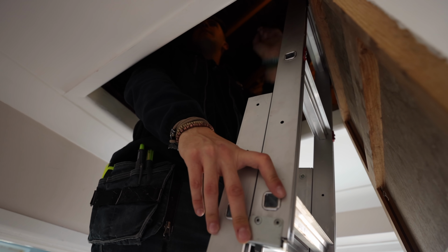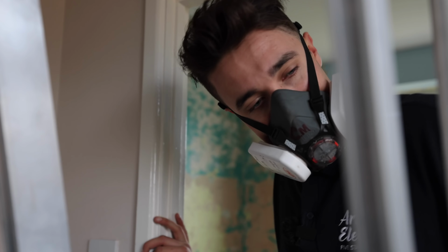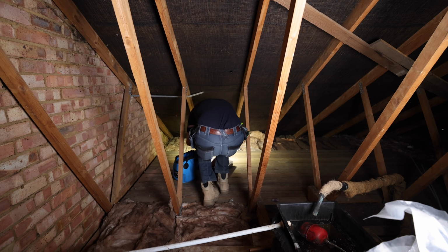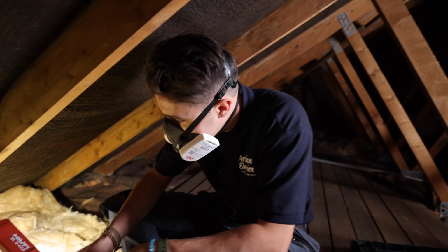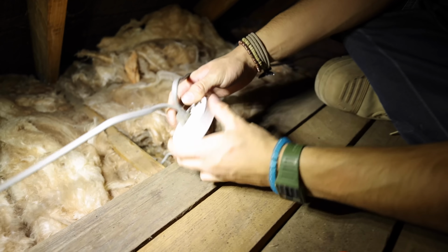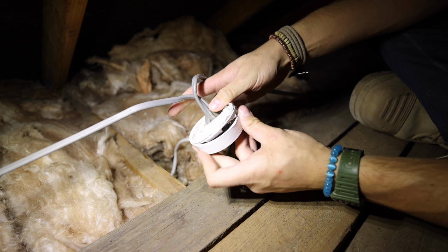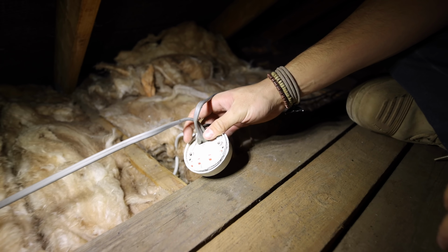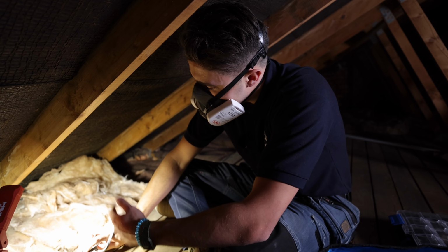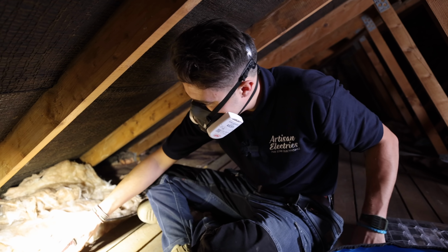All right, I'll smash this out. Exactly as expected and predicted, almost as if I already saw it on the EICR. We have this, which is so common. People put in a light fit and they go, I can't fit all those cables in there. I'll have to shove them above the ceiling and just drop the ceiling rose flex through, but that's not really the way to do it. Show you the proper way to do it.